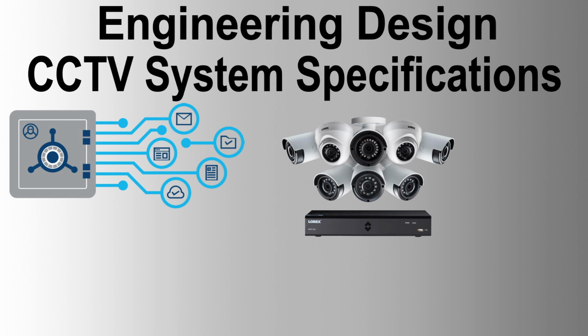System spare capacity and spares. Hardware: 20% spare capacity on interface I/O cards wired and terminated. 15% spares for cards, terminations, and slots, available but not installed. 25% expansion space in cabinets and racks for cards, terminations, and termination space.